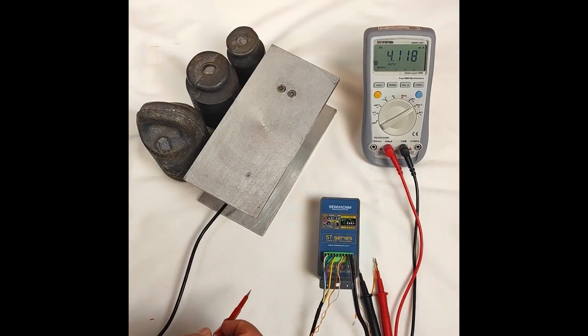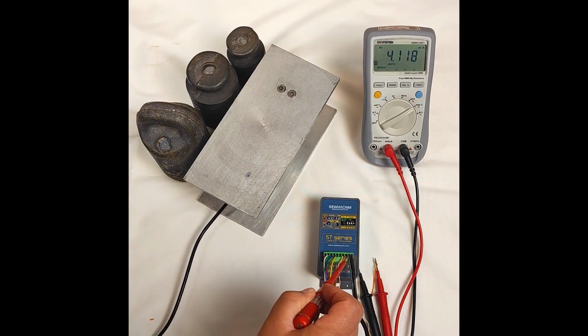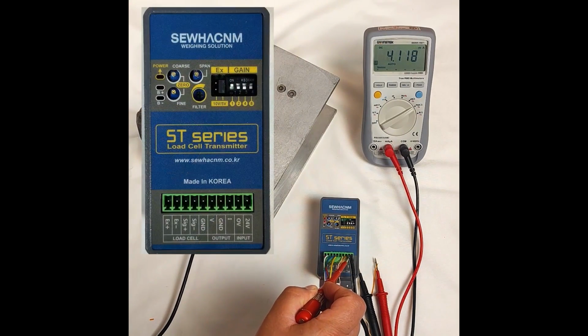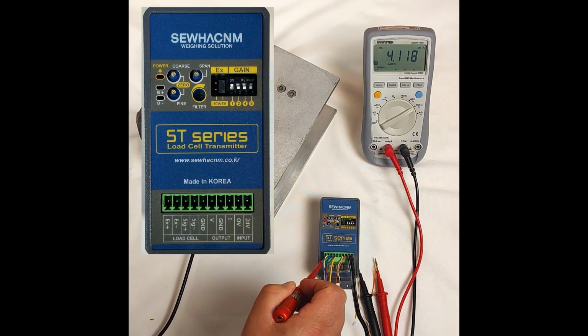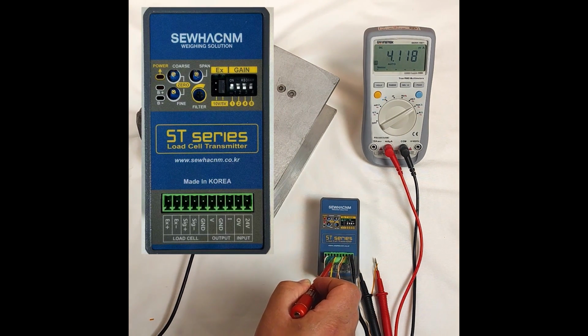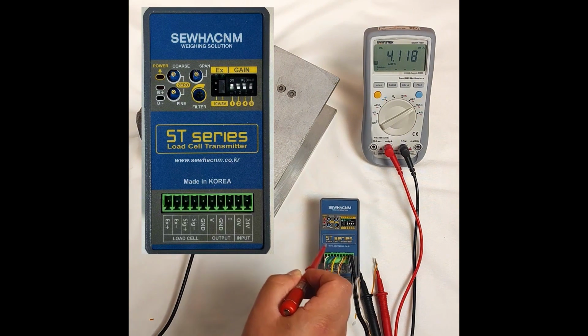Now, when we connect the load cell to the transmitter, the first step is to calibrate the transmitter. Let's go through the calibration steps together. Here we have a current type load cell transmitter. As you can see, it has an adapter here that we've plugged in to provide us with a 24 volt supply. In this section, we've connected the load cell wires.